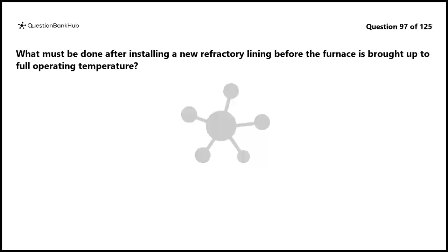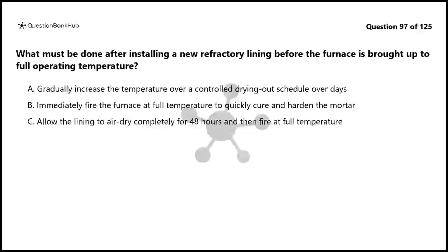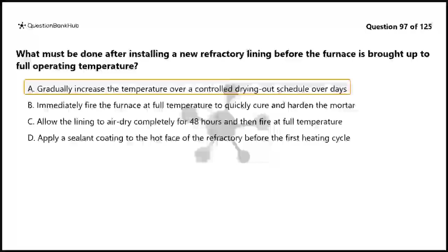Question 97. What must be done after installing a new refractory lining before the furnace is brought up to full operating temperature? After installing a new refractory lining, the furnace temperature must be increased gradually over a controlled drying out schedule, typically over several days, to allow moisture in the mortar and refractory materials to evaporate slowly.